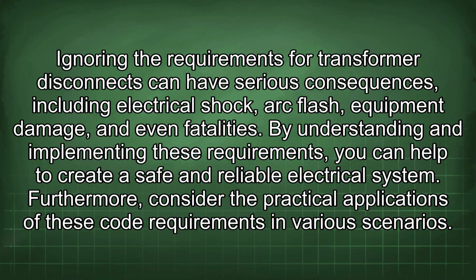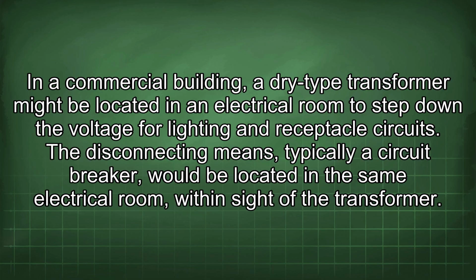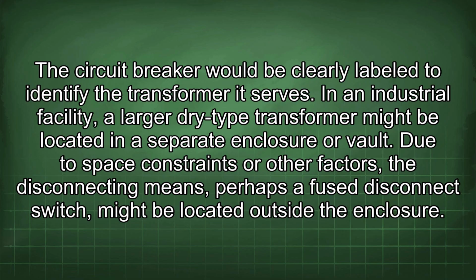Furthermore, consider the practical applications of these code requirements in various scenarios. In a commercial building, a dry-type transformer might be located in an electrical room to step down the voltage for lighting and receptacle circuits. The disconnecting means, typically a circuit breaker, would be located in the same electrical room within sight of the transformer. The circuit breaker would be clearly labeled to identify the transformer it serves.